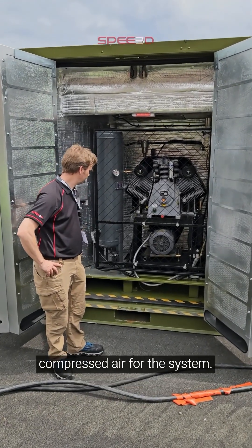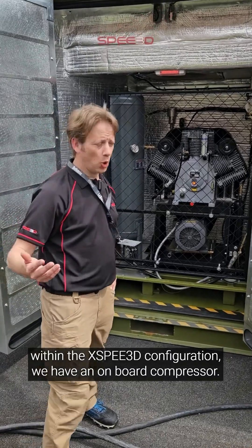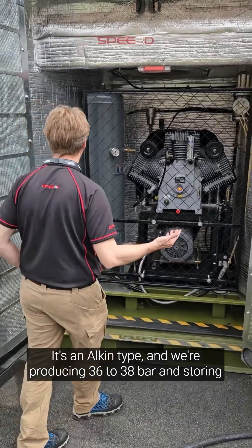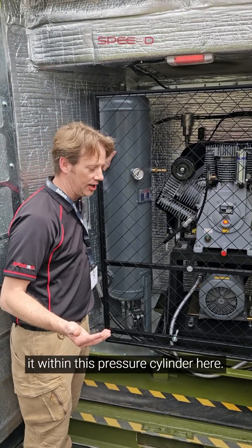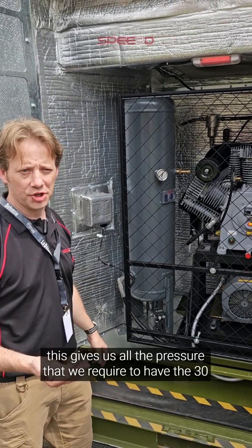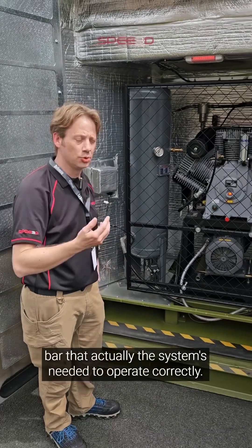Let's talk about how we make compressed air for the system. Within the XSPEE3D configuration, we have an onboard compressor — it's an Alkin type — and we're producing 36 to 38 bar, storing it within this pressure cylinder here. This gives us all the pressure we require to have the 30 bar that the system needs to operate correctly.